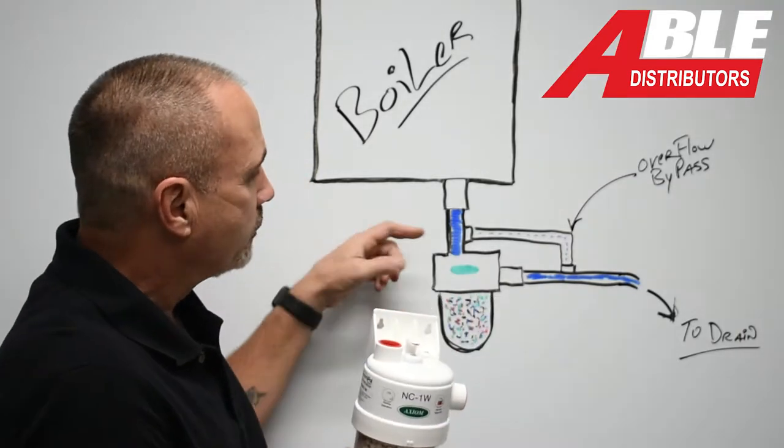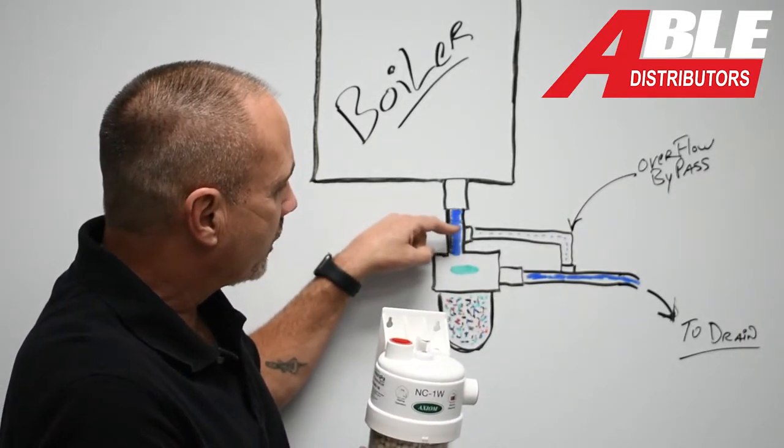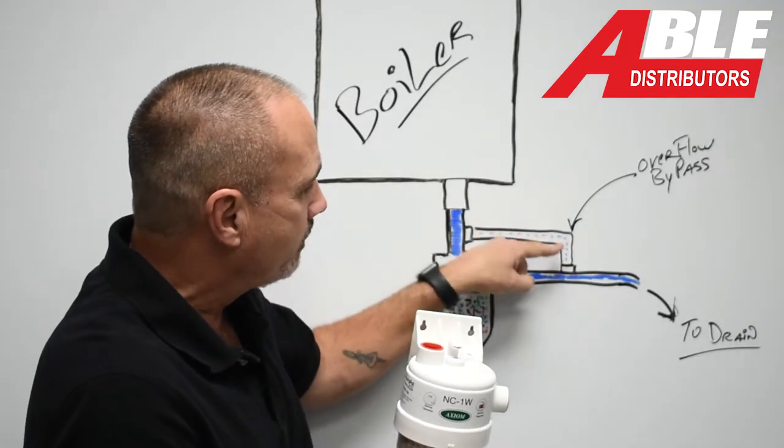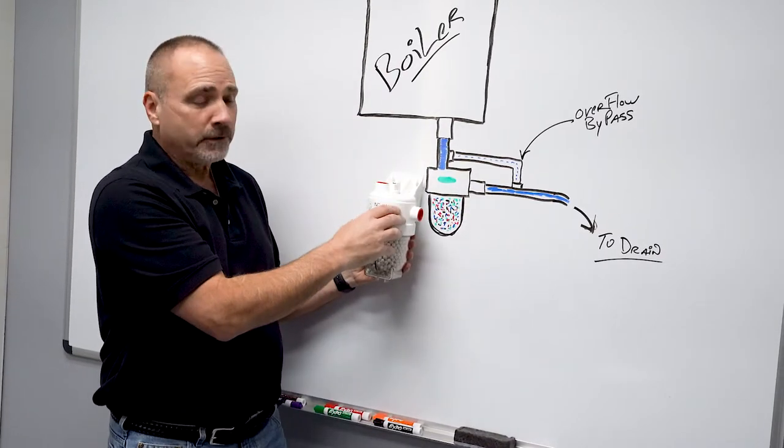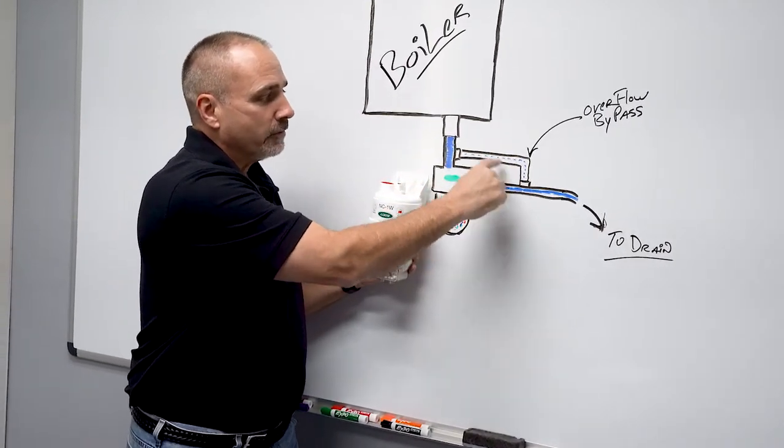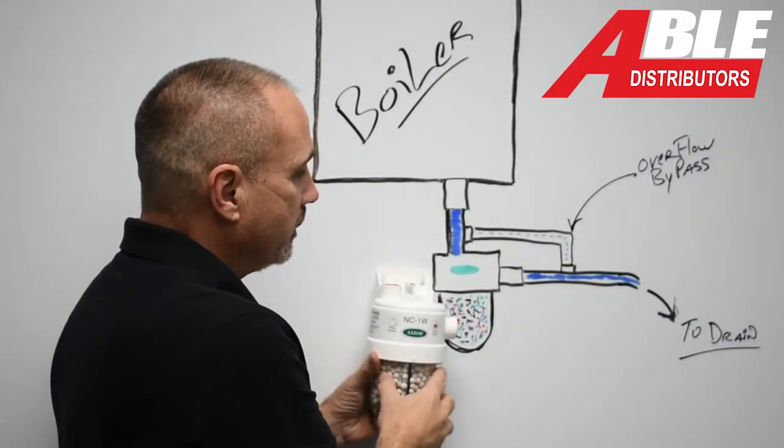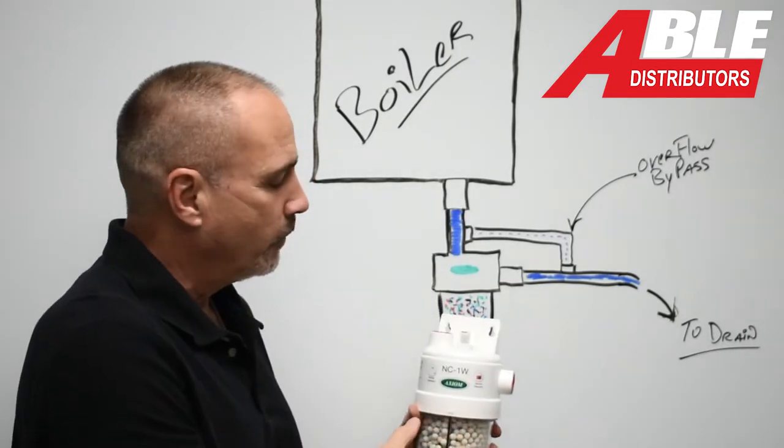What I always recommend is go with a T and do a bypass overflow. So if this ever gets full to the point where it's going to start backing up into the boiler, it just goes in a little bypass route. That way you're set no matter what.